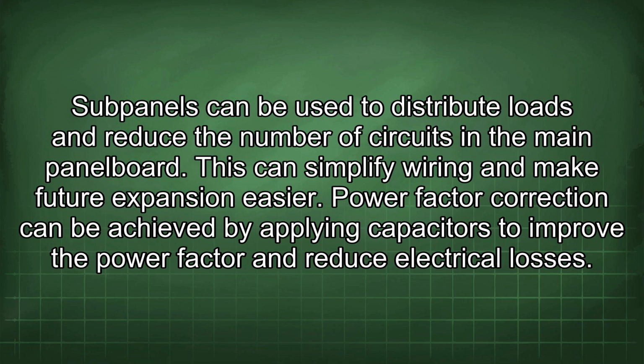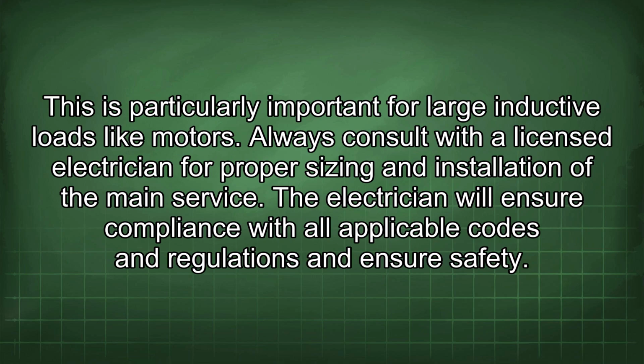Subpanels can be used to distribute loads and reduce the number of circuits in the main panel board. This can simplify wiring and make future expansion easier. Power factor correction can be achieved by applying capacitors to improve the power factor and reduce electrical losses. This is particularly important for large inductive loads like motors. Always consult with a licensed electrician for proper sizing and installation of the main service. The electrician will ensure compliance with all applicable codes and regulations and ensure safety.